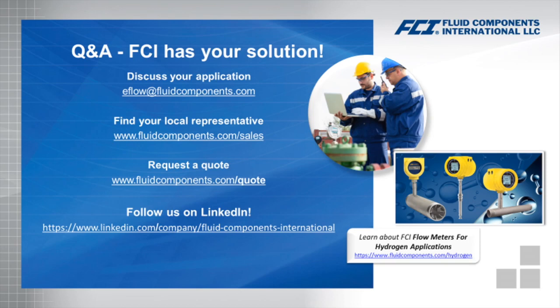The process connection for the meter looks to be a screwed connection. Have you had issues with leakage or high pressure installation? Example, less than 20 bar? Again, when you look at process connections, I think you've got that safety factor in there. Typically, when you get into higher pressures, you'll see less use of threaded connections, whether they be female or male NPT. You'll see maybe a fixed NPT connection where there's no gland involved and it's a fixed length, and you'll see a lot of flange connections. Typically you're going to see more flange connections in these higher pressure hydrogen applications.